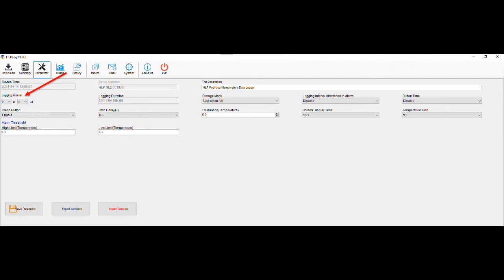Logging interval. This setting allows you to adjust how often the unit is taking a temperature recording. From standard, the unit is set to every 5 minutes, however it can be set from 1 minute through to 24 hours. Adjusting this setting will change the logging duration, which is a forecast of the memory available to use before the recordings are overlapped with new data. You are able to adjust that setting by changing the storage mode from circular logging to stop when full.